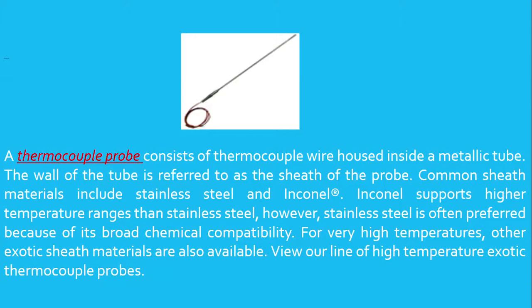A thermocouple probe consists of thermocouple wire housed inside a metallic tube. The wall of the tube is referred to as the sheath of the probe. Common sheath materials include stainless steel and Inconel. Inconel supports higher temperature ranges than stainless steel. However, stainless steel is often preferred because of its broad chemical compatibility. For very high temperatures, other exotic sheath materials are also available. We offer a line of high temperature exotic thermocouple probes.